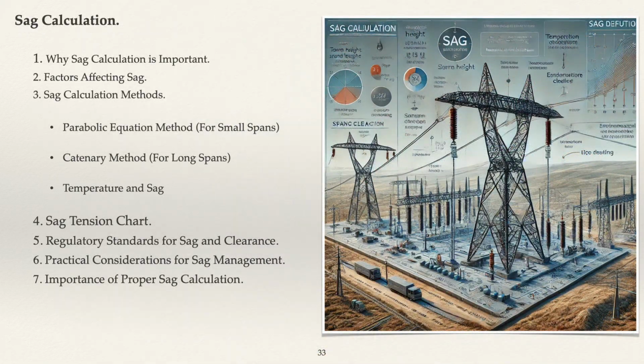Sag calculations. Sag refers to the vertical distance between the lowest point of a conductor and an imaginary straight line between the two supporting towers. Proper sag calculation is essential for ensuring the transmission line operates safely and efficiently. Too little sag can cause excessive tension in the conductor, risking mechanical failure, while too much sag may result in inadequate ground clearance or midspan clearance violations. 1. Why sag calculation is important. 2. Factors affecting sag. 3. Sag calculation methods. 4. Sag tension chart. 5. Regulatory standards for sag and clearance. 6. Practical considerations for sag management. 7. Importance of proper sag calculation.